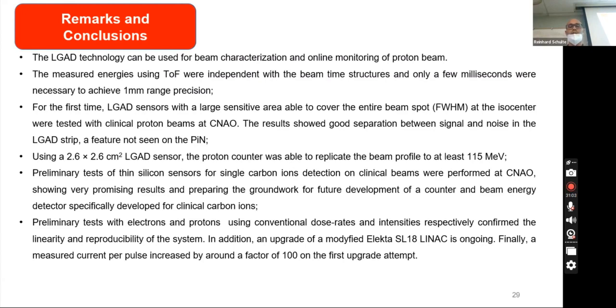at least 115 MeV. Preliminary tests in thin silicon sensors for single carbon ion detection on a clinical beam were performed, showing very promising results and preparing the groundwork for future development of a counter and beam energy detector specifically developed for clinical carbon ions. And finally, preliminary tests with electrons and protons using conventional dose rate and intensity respectively confirm the linearity and reproducibility of the system. In addition, an upgrade of a modified Elekta SL18 Linac is ongoing. Finally, the measured current per pulse increased by around a factor of 100 from the first upgrade attempt. Thank you.